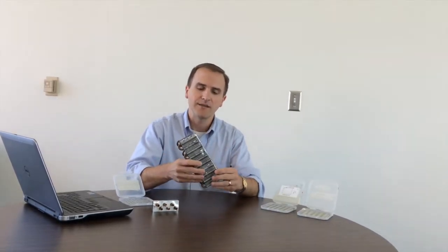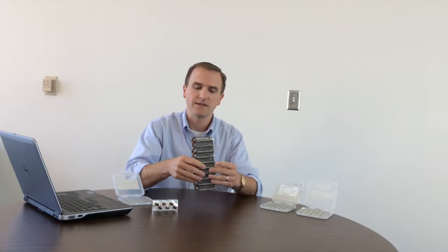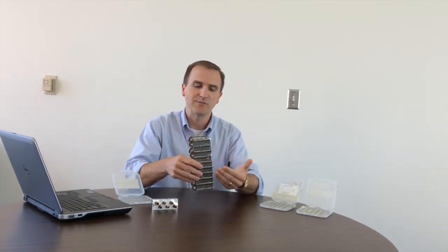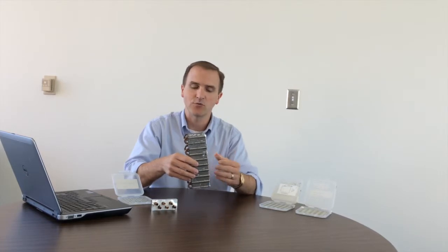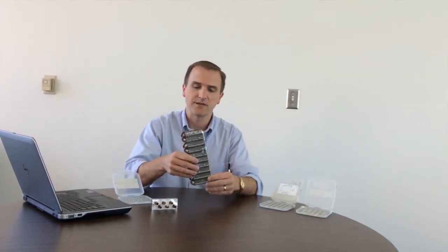And the retention of water on the heat exchanger can also lead to bacterial growth and biological activity. Legionella bacteria is one that often is associated with wet, dirty heat exchangers. So our work was aimed at trying to more efficiently drain water, condensate, from the heat exchanger in an effort to improve these three things.